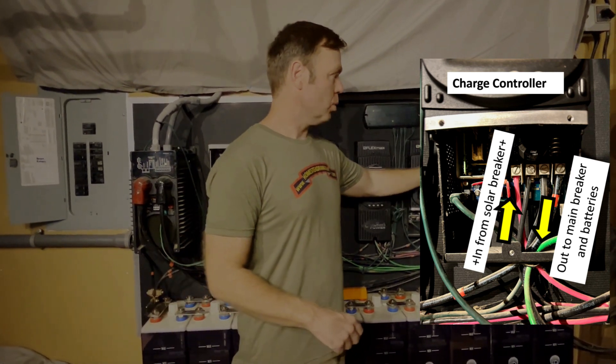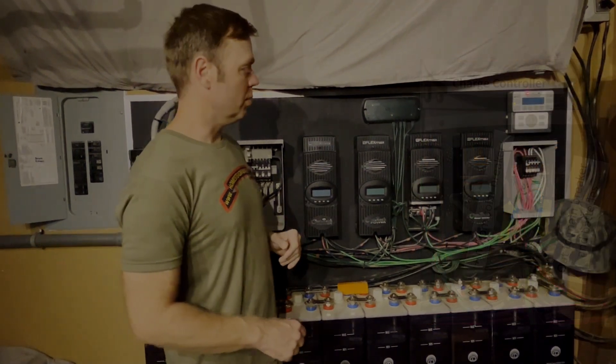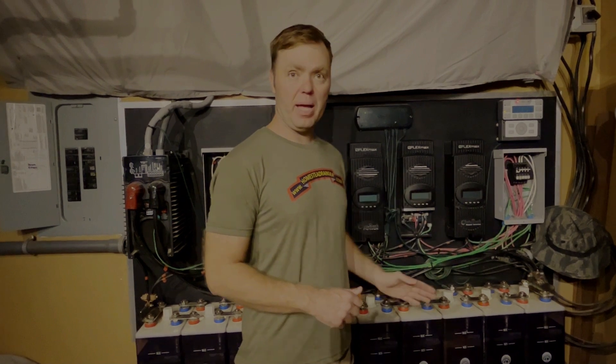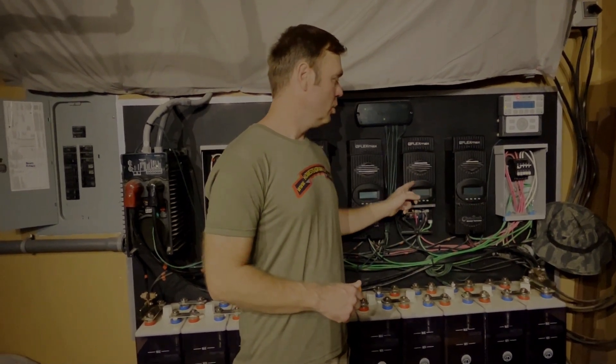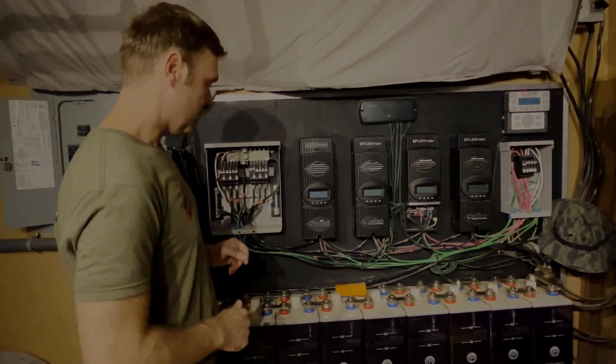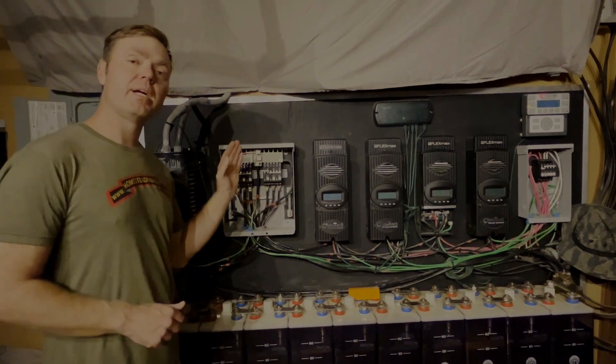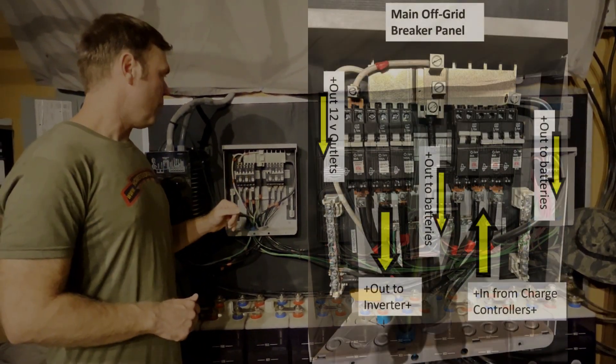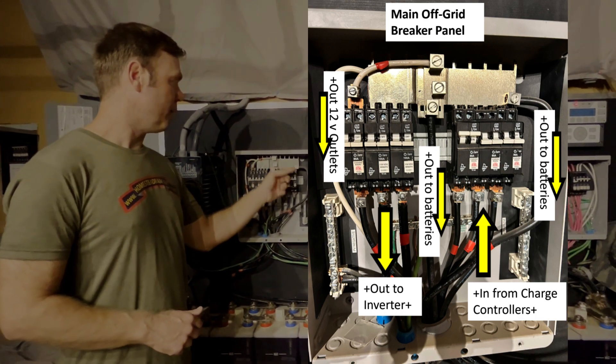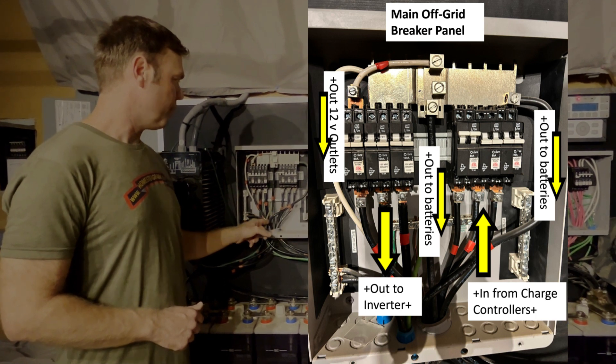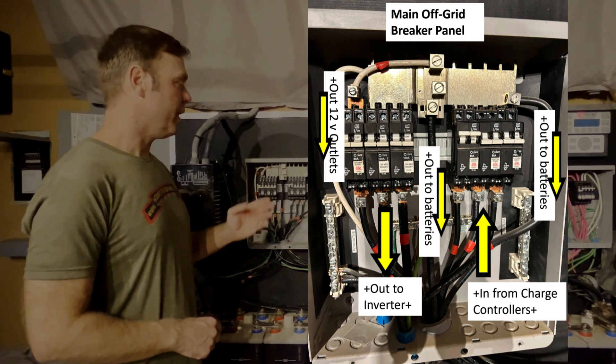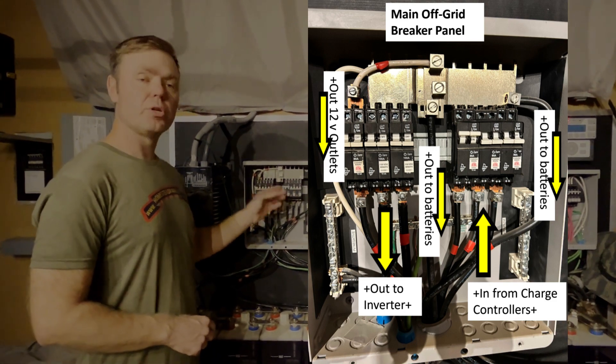After the wires come out of the charge controllers, the negative goes directly to the negative side of our battery bank. The positive goes through the circuit breakers from the charge controller, and then instead of going straight to the positive side of the battery bank, it's going to come over here to the master breaker box. The positives come in and get combined at this top combining plate, and then they go through a bigger wire. In this case, we're using a two-gauge wire, and that goes to our battery bank to charge our battery bank.